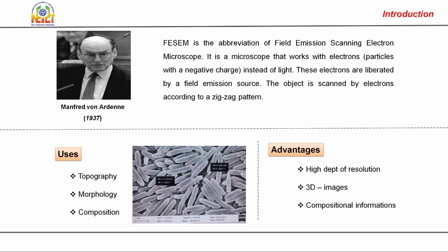This instrument is used for the study of morphology, topography and elemental composition for different samples from different fields of research like material science, biological science, chemical science, geological science, etc. The advantage of the instrument is that it has high depth of resolution, that is we can record images at high magnification, up to 5 lakh x with 1.25 nanometer resolution. We can also have 3D images and the elemental composition with this instrument.